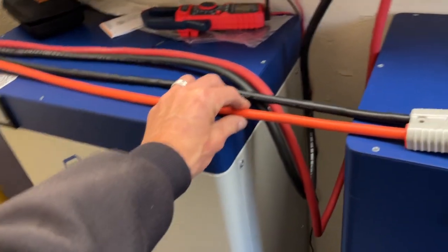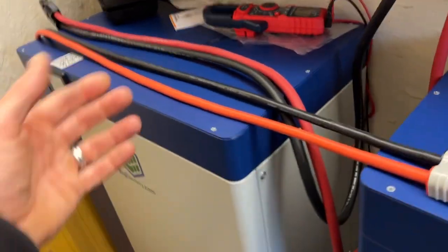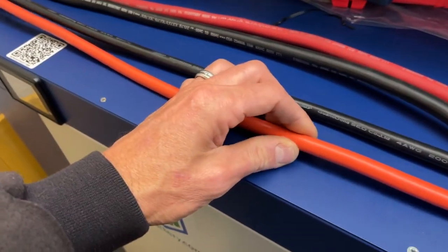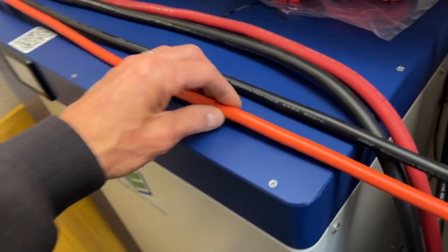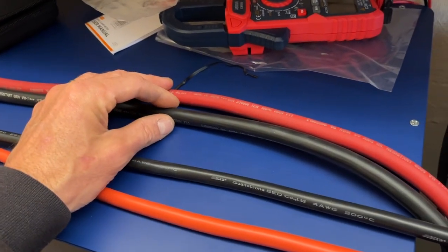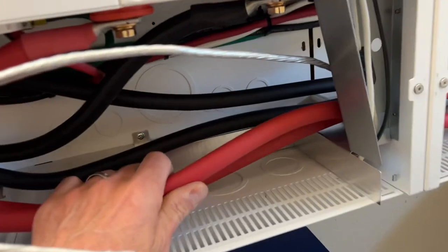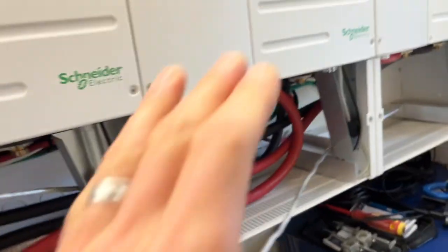I don't trust that long term. I'm looking at building a 30, 40, 50 year system here, and your insulation - you heat and cool, heat and cool - after that many decades you're going to degrade your insulation. So you don't want to run high heat. By running larger conductors, you're not going to heat up. These guys ran four ought from the inverter to the battery connect point.